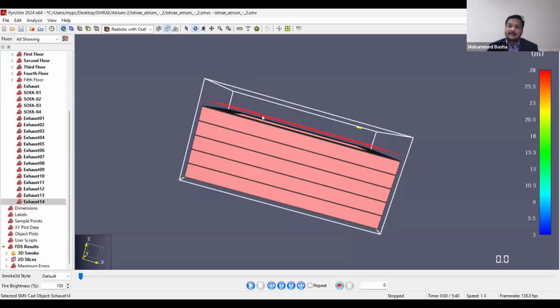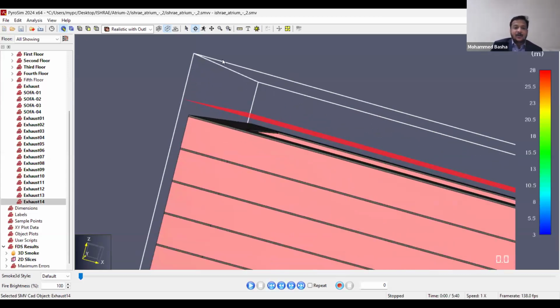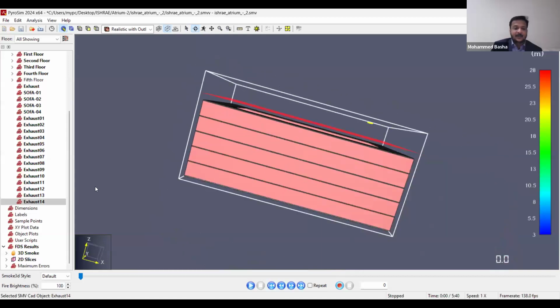It is not that I have a fan, so it should extract. It will extract, but it will not give you tenability. Because this is what we generally think as mechanical guys, right? I have a fan, I have a flow rate, it should extract. That's the design, but it will not. You need to give the proper height also. So here I have allowed up to this height, which is the D in the Excel sheet. Now let us see what's happening.